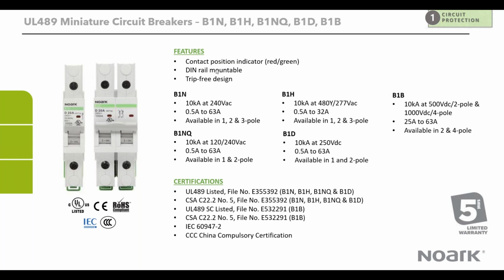Let me just mention the key features here. So you have the contact position indicator. I've mentioned that before, and that's this portion here in the miniature circuit breaker, which tells you the status of the breaker. Basically it tells you whether it is on or off. They're all DIN rail mountable. It's also a trip-free design, which is a fail-safe design that ensures that even when the breaker toggle is stopped in the on position, if there is a fault, you get a trip on the breaker regardless of the position of the toggle. And of course, all of our circuit breakers are UL 489 listed, also CSA certified for the Canadian market.